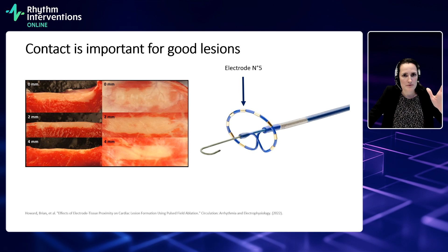The central electrode number 5, as I showed here, is at the most forward position, while no electrode exists in the most posterior position. And if you can see signals on electrode 5, you can give a little push on the catheter, and signals appear also on the other electrodes. Furthermore, you can integrate the catheter in a 3D map, and then you can see where you are in this 3D map.